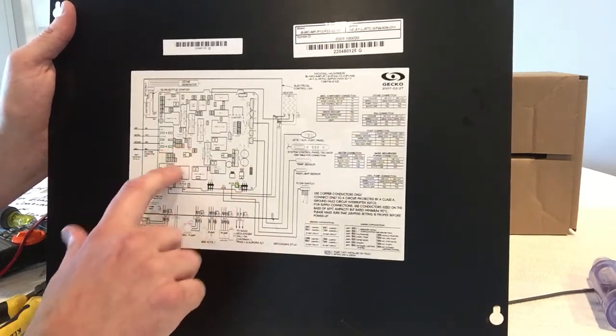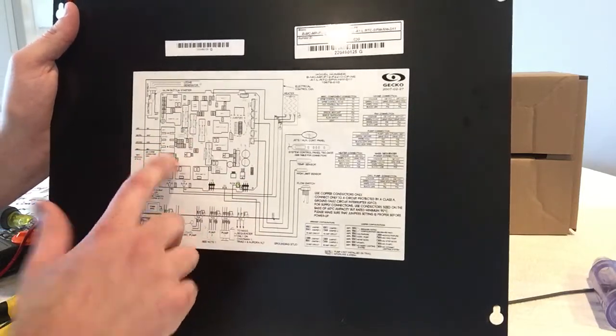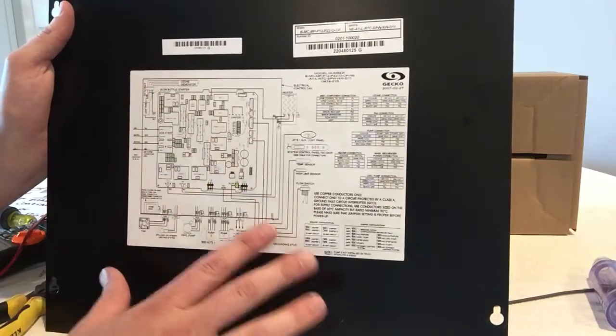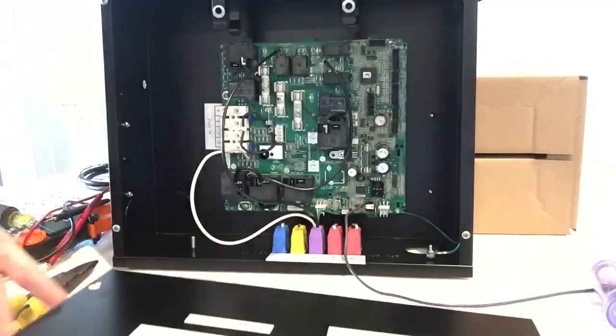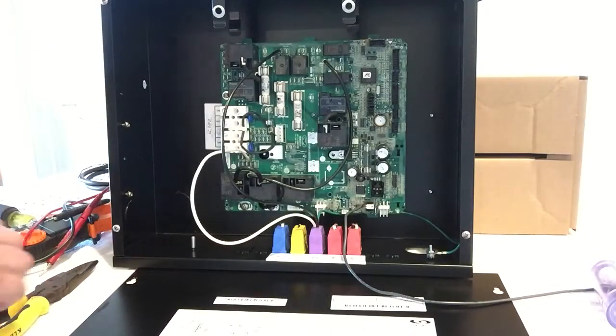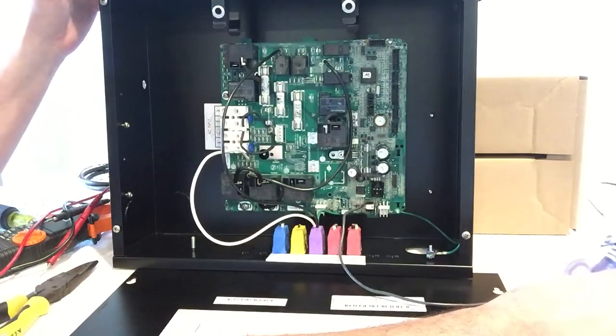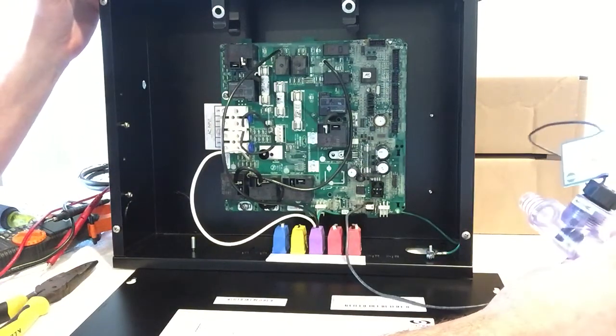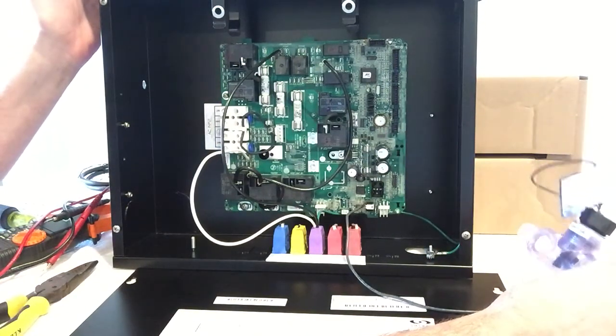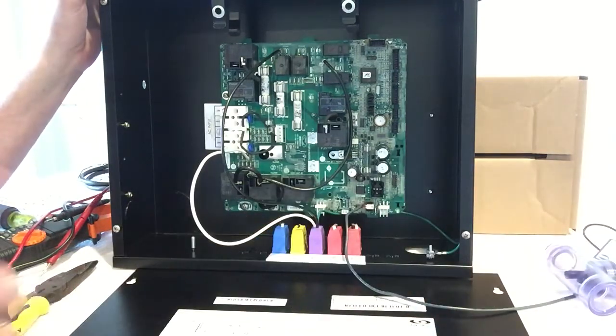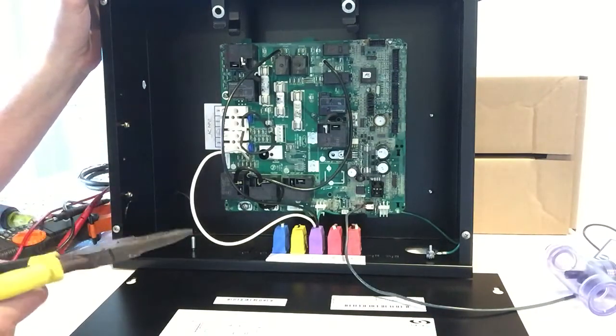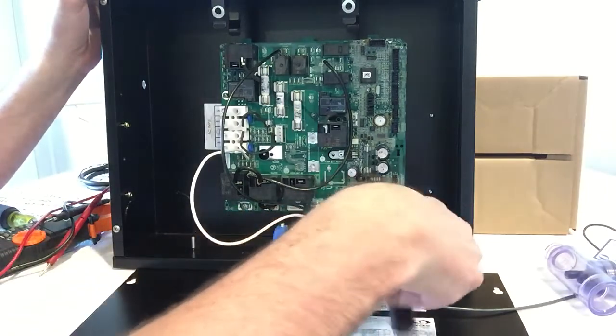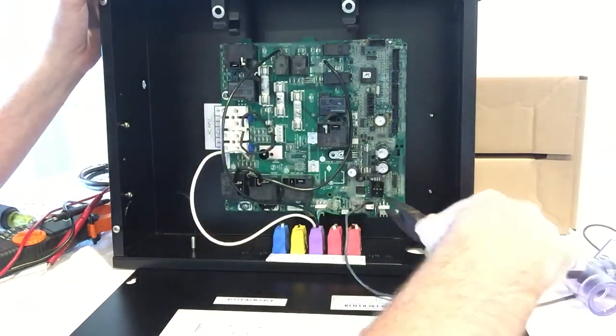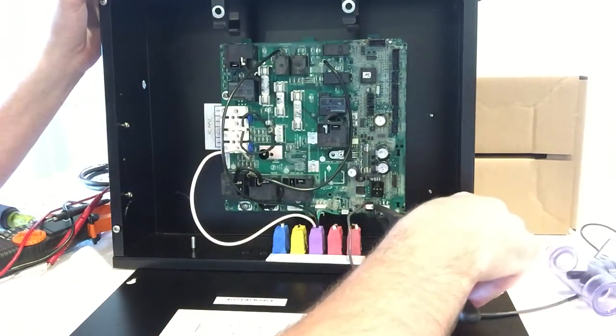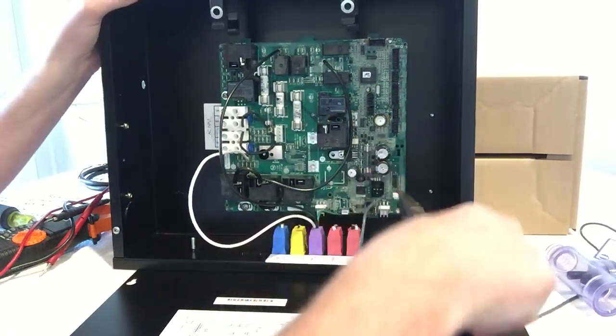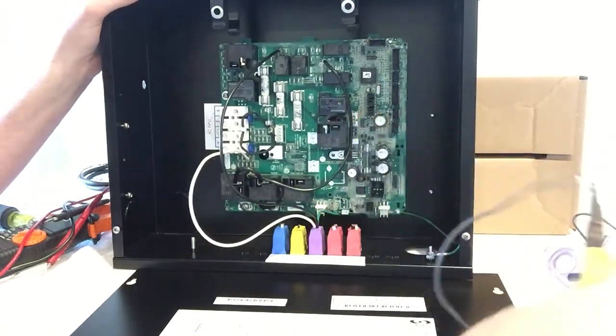And then I did these two, P41 and P54, but you could find it on your own diagram first before you locate it on the actual PC board. So, your pump's running, it's either cycling or it's running perfectly fine and you still have an error code. In this case, if it is cycling, you carefully unplug the flow sensor connector from the PC board.